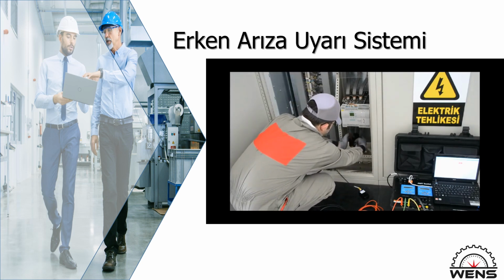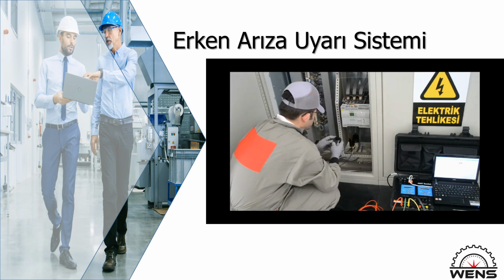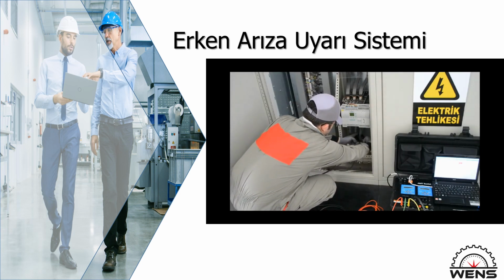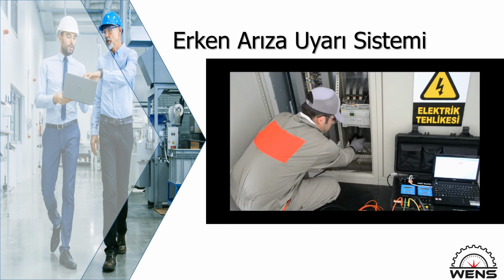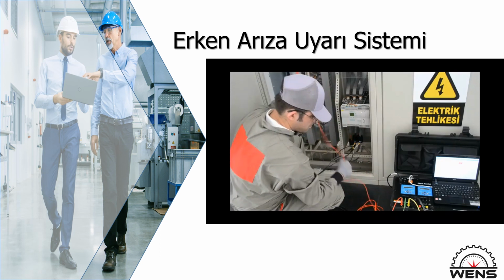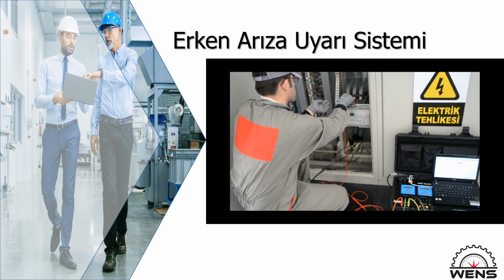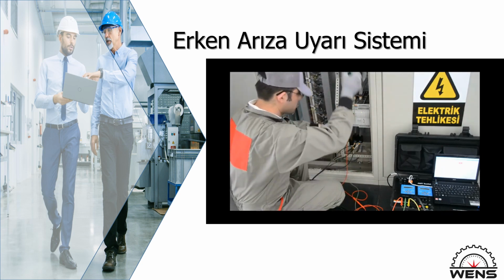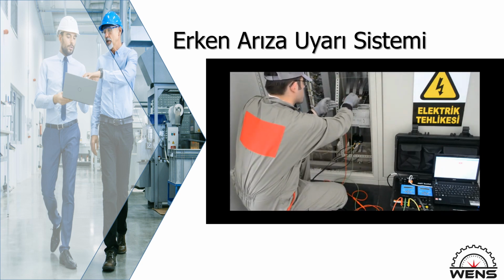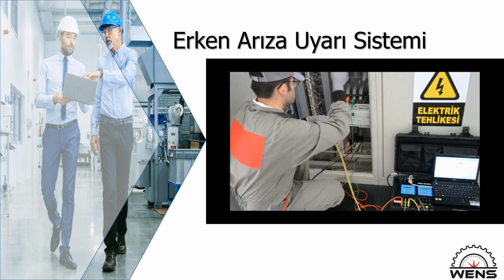Once the AMU unit is switched on, it requires minimal user configuration. AMT Toolkit is designed to acquire data with a couple of clicks. During automated learn mode, the complete normal operating condition of the connected system is established within 30 minutes. When this is complete, the software creates a complete condition assessment report for the connected equipment. Each report lists the existing faults of the motor-driven system.